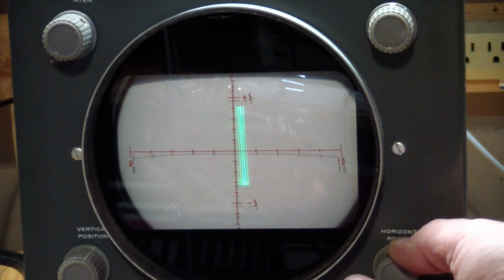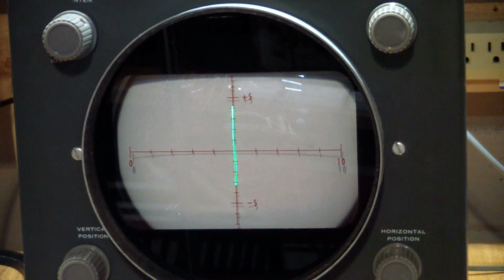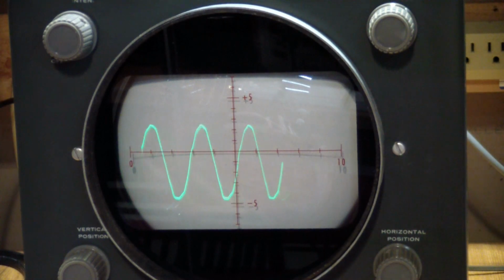It does have a few bends in it, but remember that the tube seems to be extremely sensitive to external magnetic fields, and there are things all over my lab, and it would be kind of difficult to remove them, but this verifies that the vertical amplifier works. Now we're going to check the horizontal amplifier as well as the sweep generator, which I hope we fixed by replacing the tube.